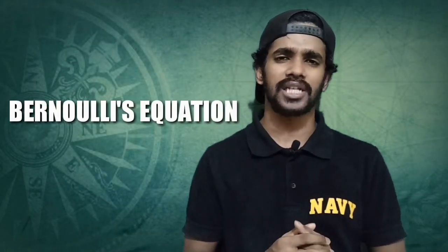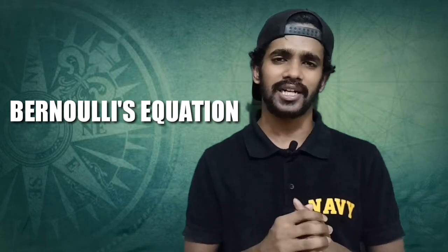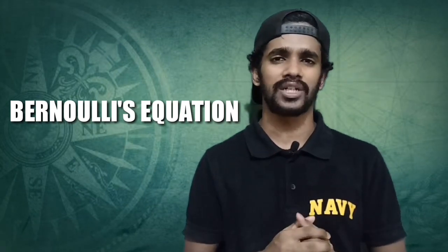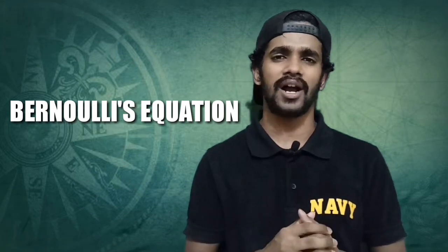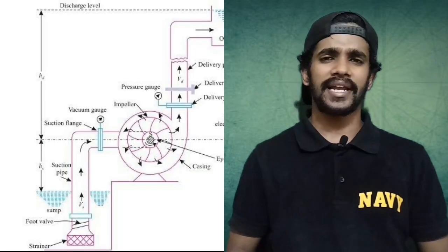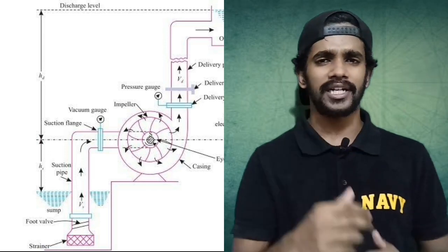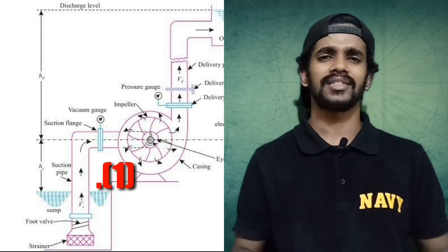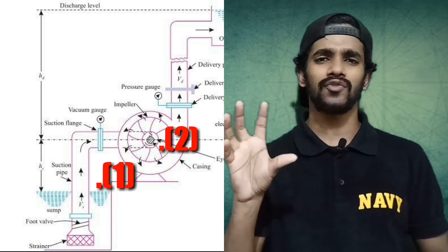To derive the Net Positive Suction Head, we will be dealing with Bernoulli's equation, which we have already studied. We will be taking two points into consideration: the first point is the sump level — that is the place from where the pump takes suction — and the second point is the eye of the impeller.